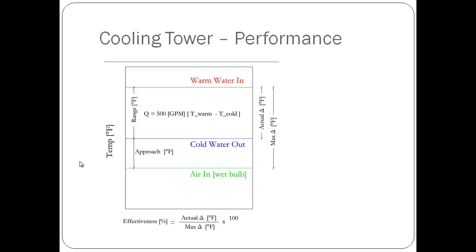The smaller the approach, the better the cooling tower is at providing cooling. The wet bulb temperature of the entering air is the lowest temperature the exiting water can reach. If a cooling tower has a zero degree approach, then the cooling tower is using all of the available heat exchange from the air to cool the water.